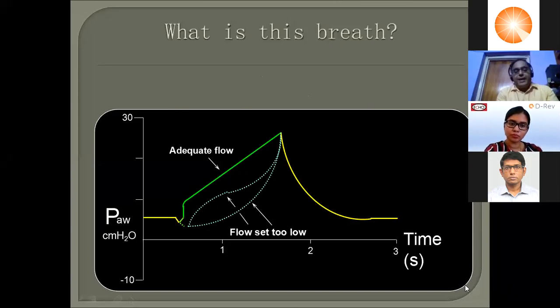Now we have something else. So what is this? So this is a pressure time scalar. Okay. So this is my Paw, and then my pressure is gradually going up. So what type of breathing is it? It is volume control breathing. Yeah. If it was pressure control, it would look like a square window. So it is a volume control. Now remember, in volume control, you have a fixed flow. The ventilator decides on the flow. Now, if your patient has a lot of air hunger, if he wants to breathe very hard, then what happens? Sometimes the flow that the machine is generating may not be enough for the patient. And if that happens, then the patient is having air hunger, and then what happens? This curve, rather than looking like this, it sags and it looks like this. So if this happens in a volume control pressure time scalar, if you see the sagging, that tells you that your patient is having air hunger.